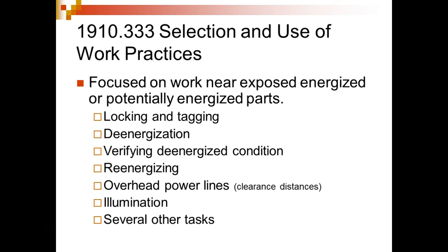de-energizing, and verifying de-energized condition. And people don't understand that. When you go out and lock out and tag out, a lot of people take for granted that they've taken power away from everything. So one of the things you're supposed to do is verify that everything's been de-energized. What do we normally use to verify? Try it? No, we don't do that. We have these things we call voltmeters. So we check things with voltmeters.